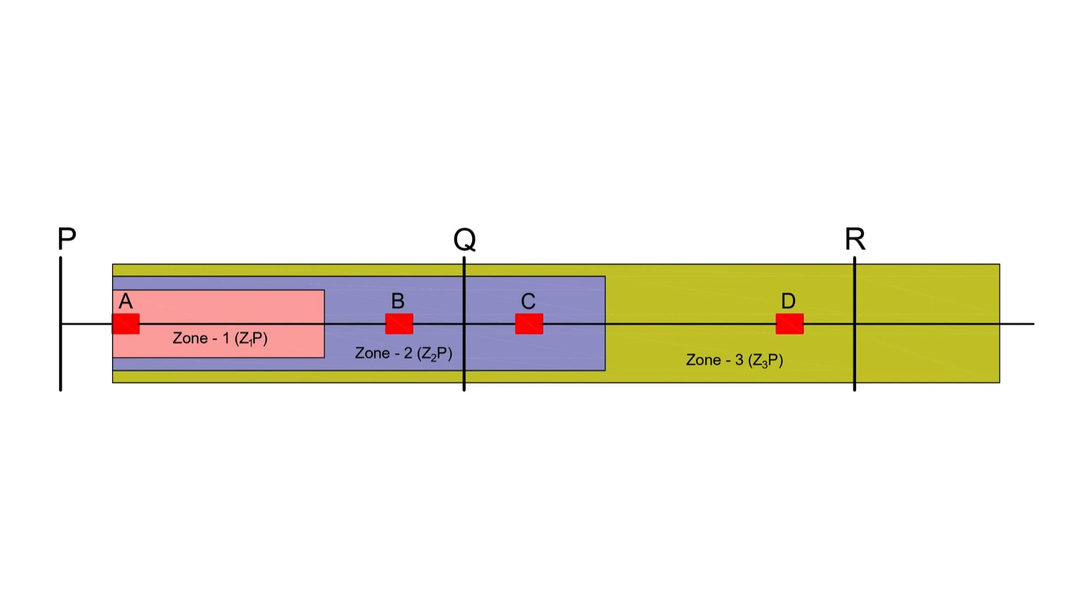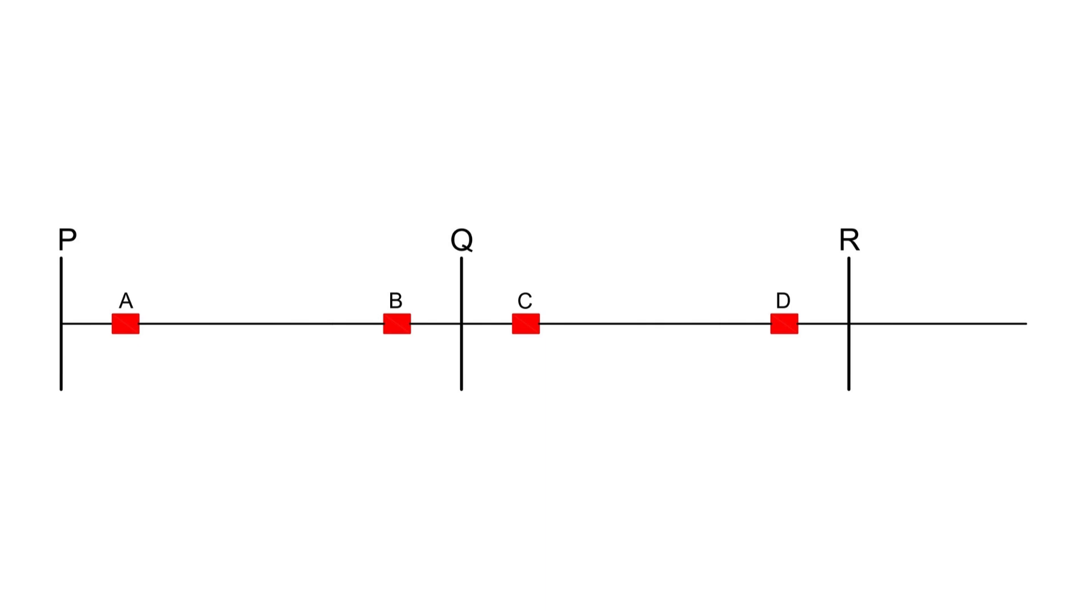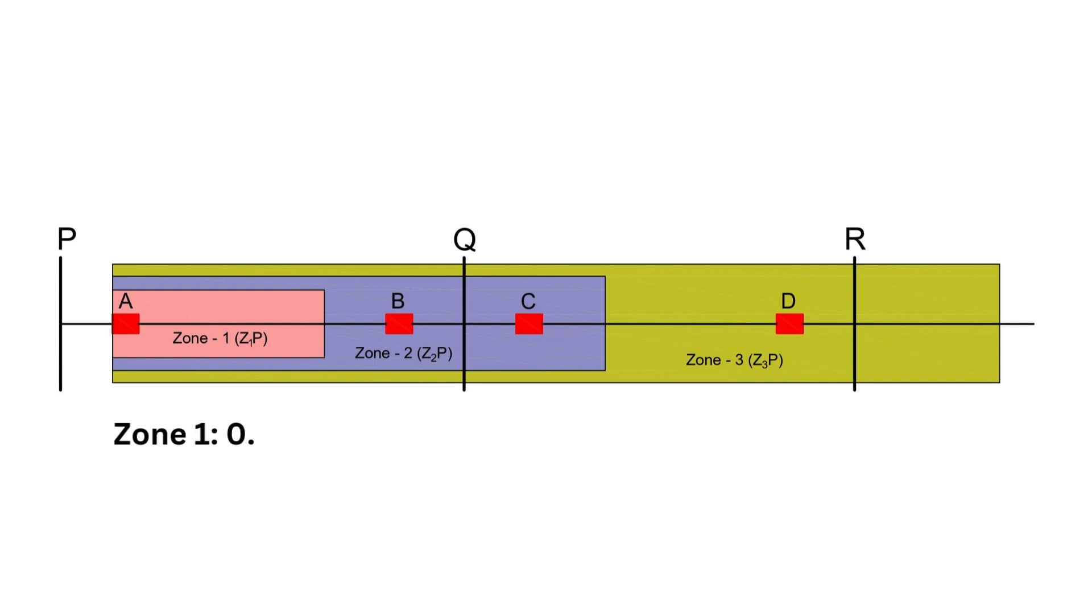Let's begin by focusing on relay A at substation P. Zone 1 is set to cover 80% of the total line length between two substations, in this case between P and Q. Zone 2 covers 120% of the protected line length, that is PQ. Zone 3 is a bit more complicated. It's set to 120% of the total length of line PQ plus the longest line connected to the next substation Q. If substation Q has two lines, QR and QS, we take QR since it's the longer line.